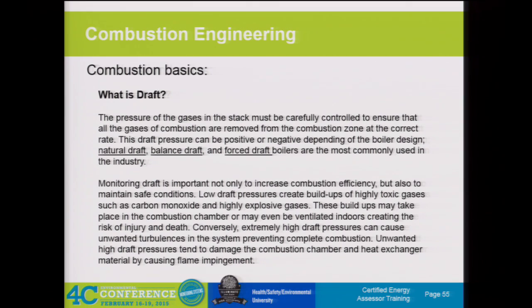Tramp air is a much worse situation for a forced draft boiler. When you're designed at certain pressures and need certain penetration into the firebox and certain pressure to create turbulence in the reaction, any inefficiencies where you're not getting that directed pressure or you're losing pressure before you get there—it impacts that ability. Also, tramp air where you're sucking in colder ambient air from outside in the negative parts of the fan is starting to impact your efficiency. If you're trying to preheat air to have hotter air going into the firebox and now you're sucking in colder outside air that hasn't been conditioned, you're dropping your efficiency at that point as well.